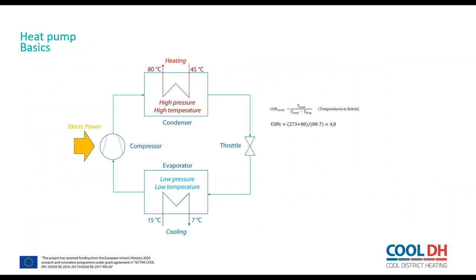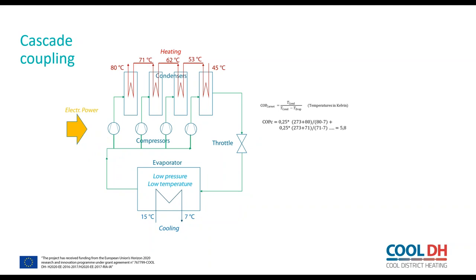This is the basic heat pump theory, where the coefficient of performance is dependent on the temperatures on the hot side and on the cold side. I think you're all familiar with this one. And what can we do to improve the COP? Well, we can split the heating on the hot side in cascade couplings, meaning that we raise the temperature incrementally, in this case in 4 steps, and the temperature difference, thus increasing the COP, is reduced. So in this case, we raise the temperature in 4 steps, the COP becomes better than the case when we only have 1 step.